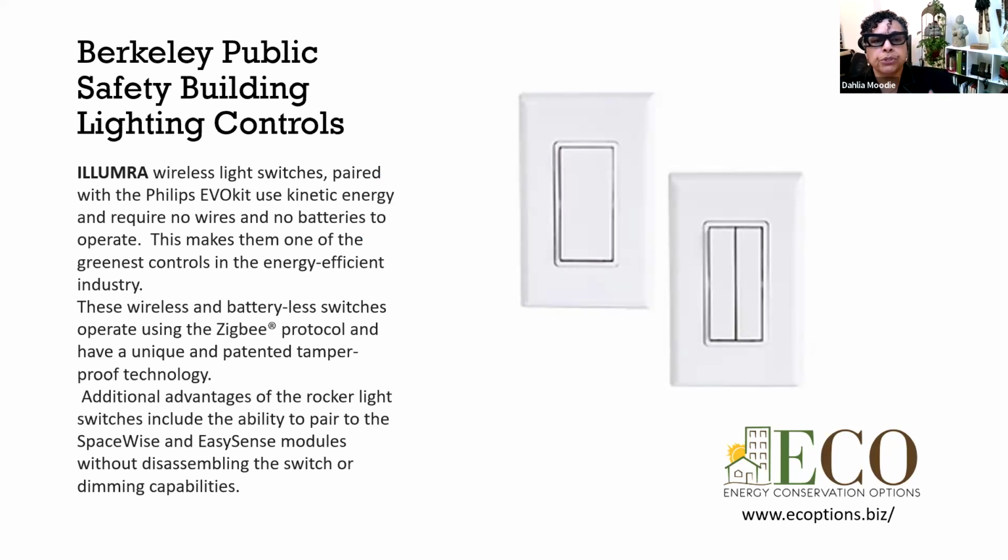Okay, so we showed you the Philips fixture earlier, that is the integrated fixture that we use in the general lighting area. And one of the really nice things about the Philips, and this idea of making it more feasible and affordable to have controls, is that they're able to use a control that's called Illumra. And that Illumra switch actually uses kinetic energy in order to send a signal to the fixture and communicate what is necessary, whether it's dimming, off, on, and or the idea that you also still have the integrated controls for occupancy in that fixture when it's necessary.